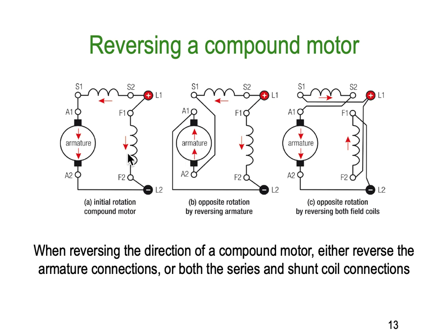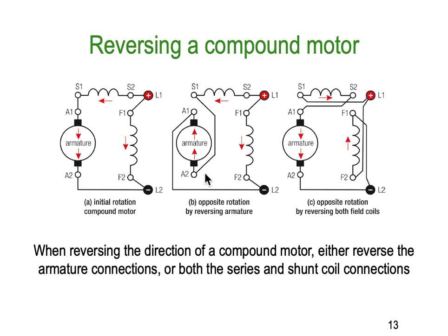Reversing a compound motor: the same principle applies — you've got to reverse either all the field or the armature. When reversing a compound motor, either reverse the armature connections or both the series and shunt coil connections. In arrangement B, everything stays the same but we've simply reversed the armature connections end to end. In arrangement C, the armature stays in the same direction but we reverse both the series and shunt field connections — you must reverse both parts of the field in a compound motor.